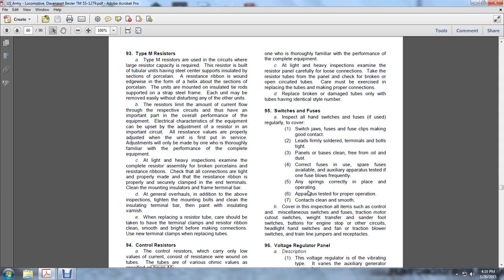A light and heavy inspection: examine the complete resistor assembly for broken porcelain and resistance ribbons. Check that all connections are tight and properly made, and that all resistance ribbons are properly secured in the clamps at the end terminals. Clean the mounting insulators and the frame terminal bar. At the general overhaul, in addition to the above inspection, tighten the mounting bolts and clean the insulation terminal bar. Then paint with insulation varnish.